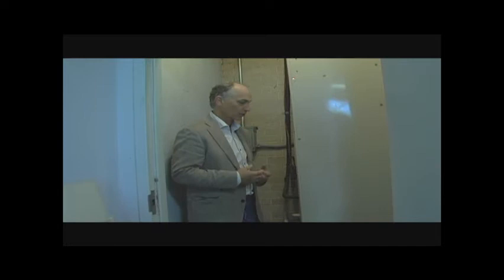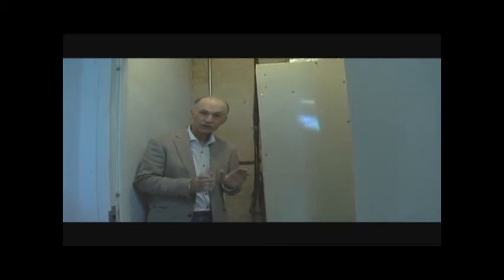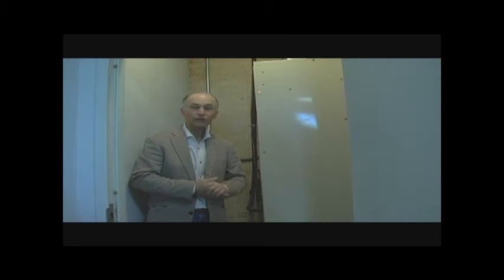This is part two of looking at how this system was originally put together, why it was wrong, and how we could determine what was going on. We have a heat pump air handler. We'll show you where the old return air vent just came to this room — the metal down here was just an open filter. George Gary Mechanical came in, put in a very tight turn, had this fabricated to communicate back out into the hallway. What I could feel when I did the first analysis of this space was that return air was being made up from two areas — one through a crack to the outside of the building. I can still feel a little bit of air moving through here, so outside air is coming directly into the building.